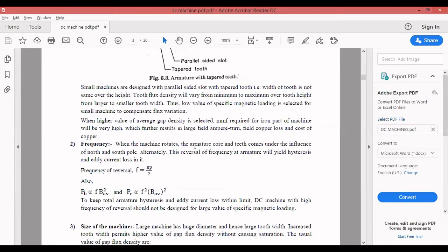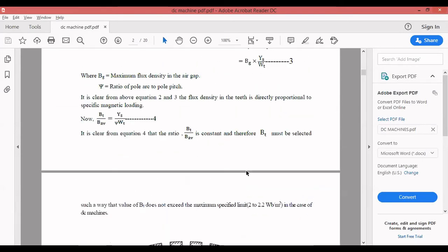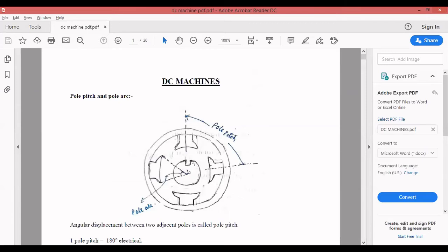Z is the total number of armature conductors, S is number of slots, Z_s is conductors per slot, A_Z is area of each conductor, rho is resistivity, and delta is current density. Specific electrical loading is nothing but A_C = I * Z / (pi * D). Dividing numerator and denominator by S gives A_C = (I * Z_s) / Y_s, where Z_s is conductors per slot and Y_s is slot pitch.